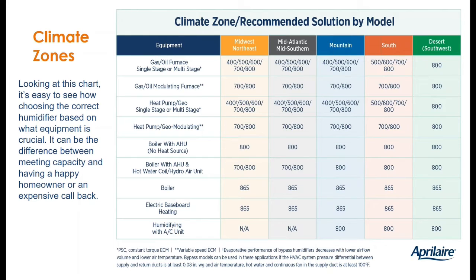The HVAC system type below it, fossil fuel modulating, this is a true variable speed system. So very uncommon. This is the high-end system. But some of the advantages are obviously it's going to have a variable CFM and a variable BTU output. And so because of that, remember, water, airflow, heat are the three things we need. Sometimes we may not have a lot of airflow and we may not have a lot of BTUs available. So we get rid of our bypass units because of the airflow issue, and we pick larger capacity units because of the lack of BTUs.